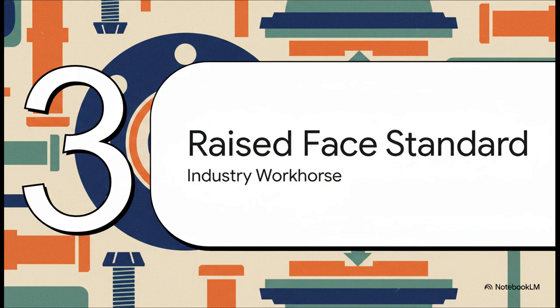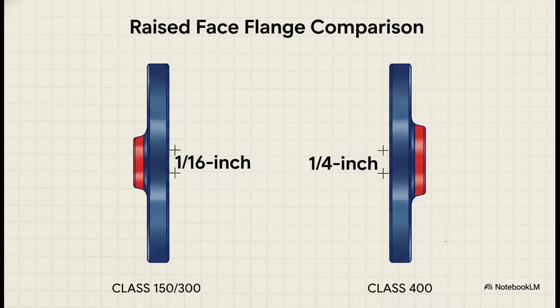Let's step it up. Section 3, raised face, the standard. Let's see how this builds as we enter the realm of the undeniable workhorse of the process industries. Now, what's really interesting here is how a tiny fraction of an inch completely rewrites the physics of the seal. For standard pressure ratings, like your Class 150 and 300 flanges, the face stands proud of the bolt circle by just 1/16 of an inch. But step up to higher pressure standards, Class 400 and beyond, and that protrusion bumps up to 1/4 inch.